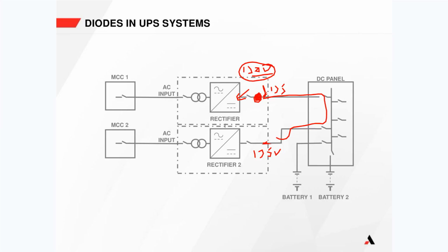And then it checks its output, and it says, wait a minute, I've still got 135 volts from this charger on my output. I'm going to phase off even more. Then it checks its feedback and it says, oh wait, I've still got 135 volts. I'm going to phase off even more. And basically what can happen is this charger will completely turn off because it's trying to regulate at 130 volts and it keeps seeing its output is 135 volts. So it will turn the phasing of its SCRs inside the rectifier bridge completely off, and you would have 0 volts inside that charger.